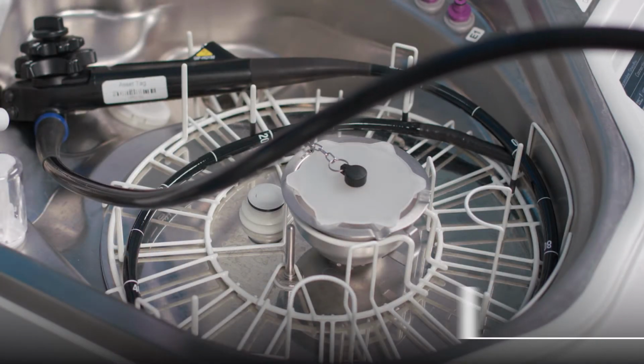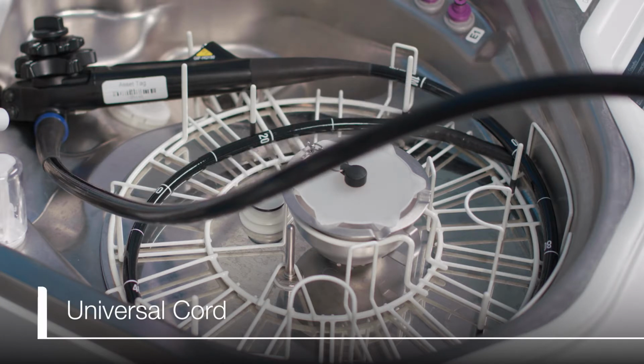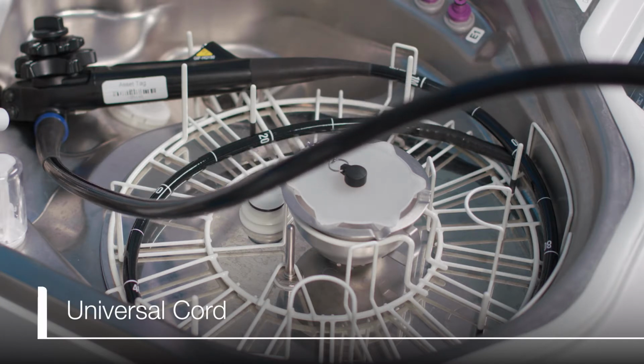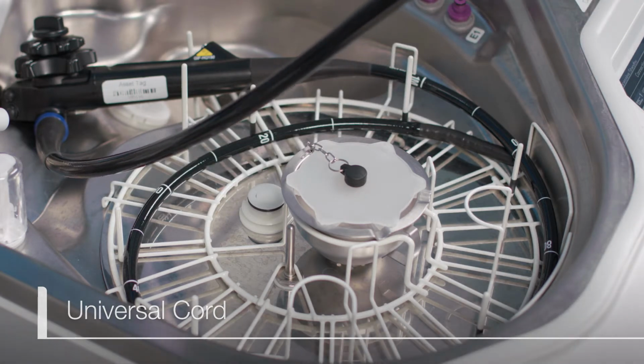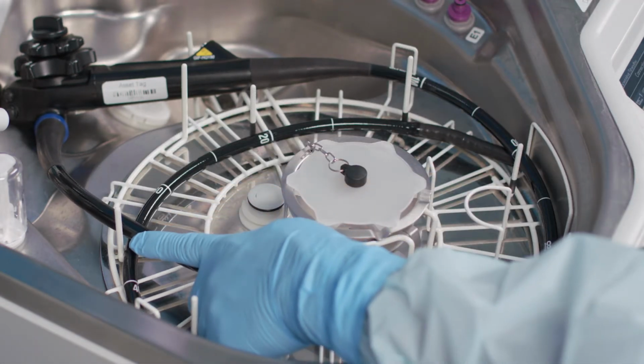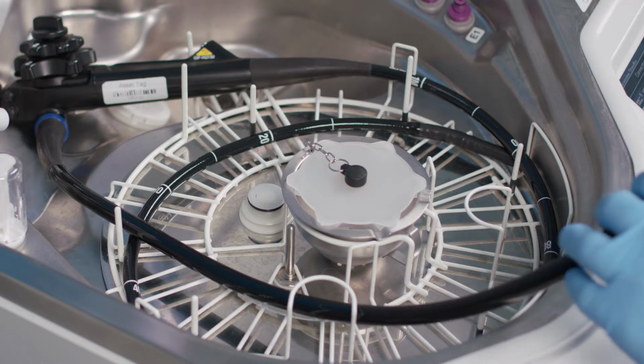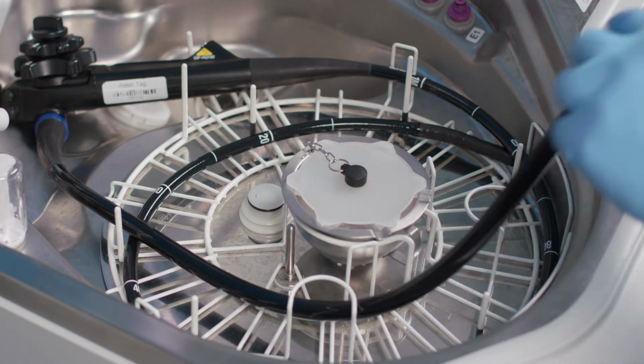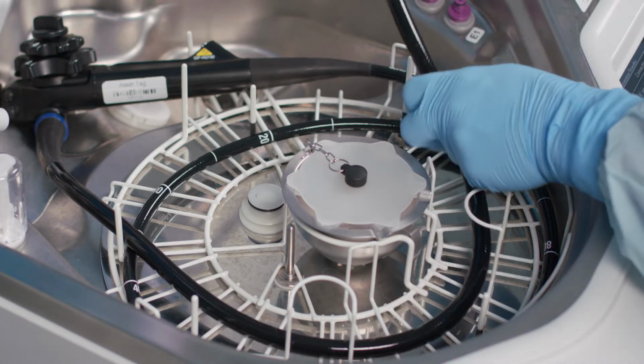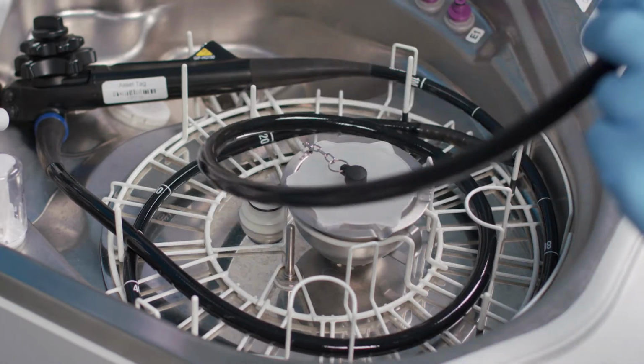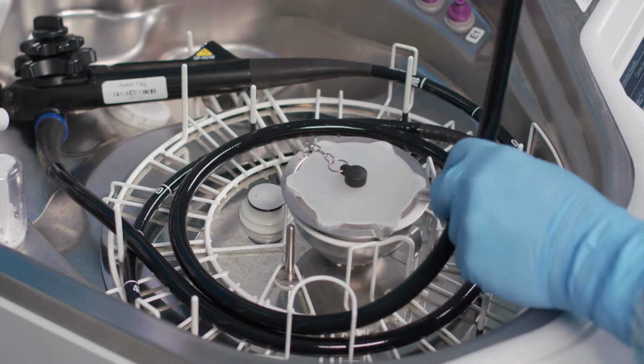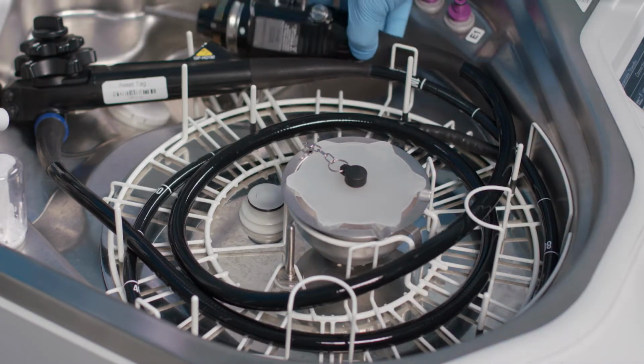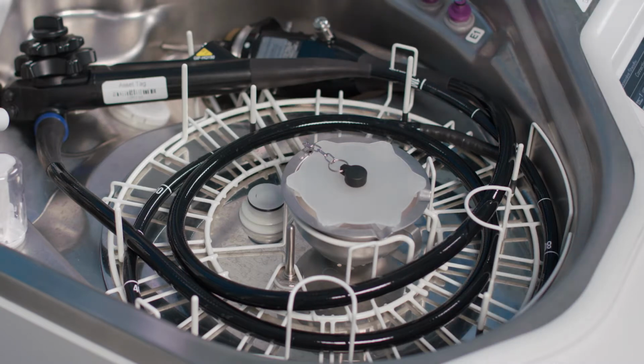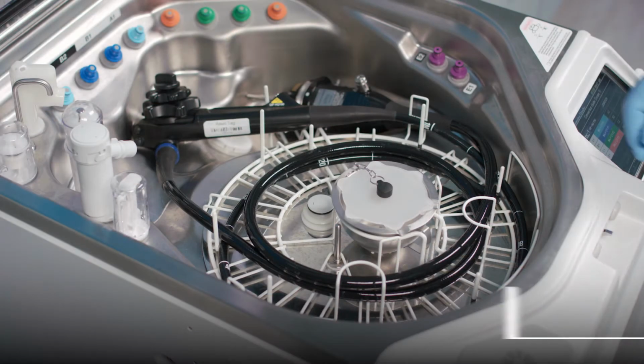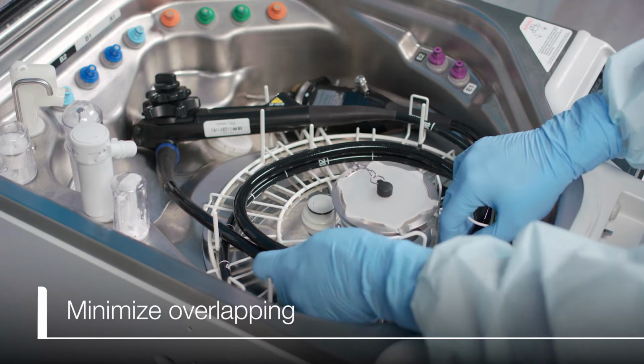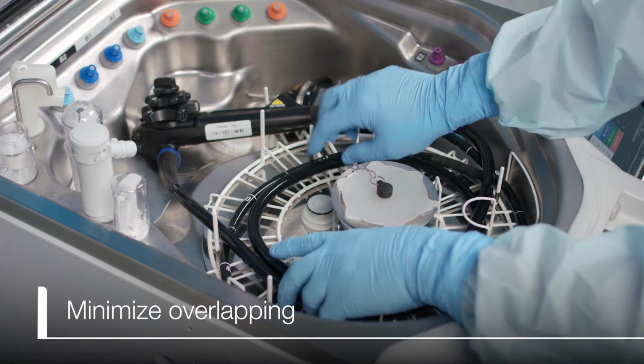Once the insertion tube and the control body are successfully loaded, it's time to wrap the universal cord counterclockwise inside the retaining rack. Remember to start by wrapping the cord to the right side of the retaining rack pin. Place the universal cord under the hook of the retaining rack. Once the cord is completely wrapped, place the scope connector directly on top of the drain port. This method will ensure the scope is loaded properly. Finally, make the necessary adjustments to minimize overlapping of the insertion tube and universal cord.